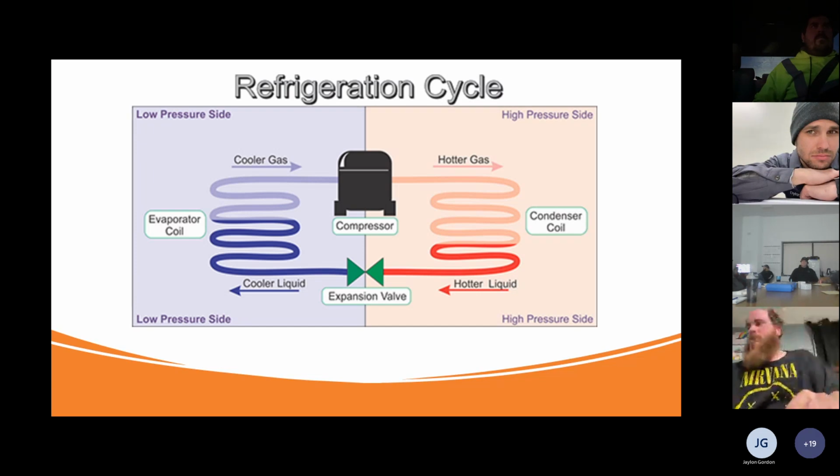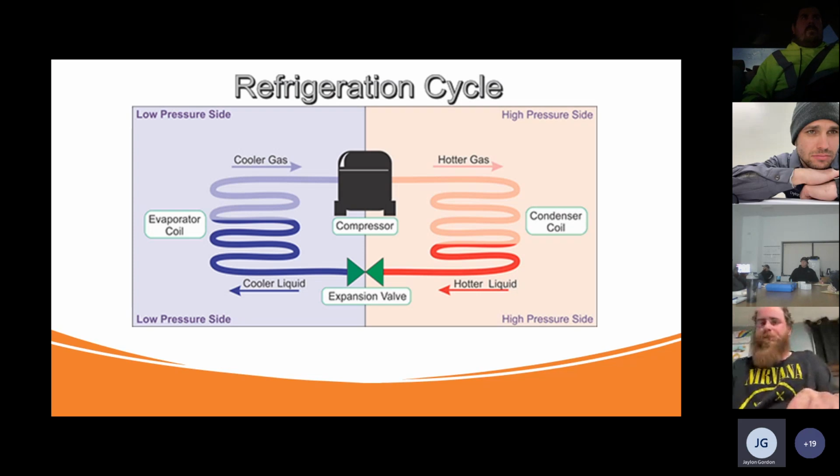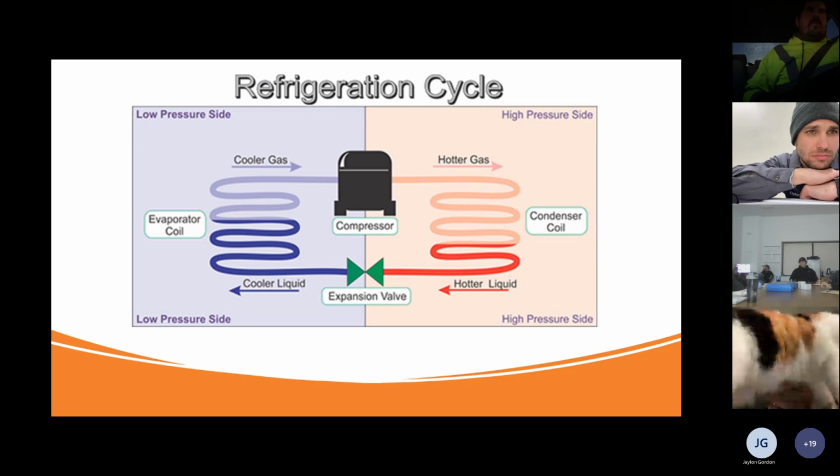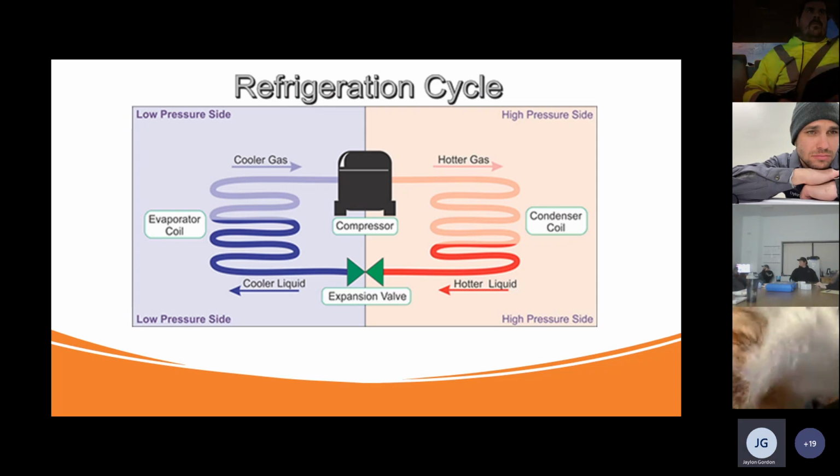You allow it to vaporize into actual vapor before hitting the compressor. Or dumping liquid into the suction of a small, self-contained unit, you're probably going to send so much liquid to the compressor, and compressors aren't designed to pump liquid. They're built to pump vapor in and push it back out. That's what I was looking for.